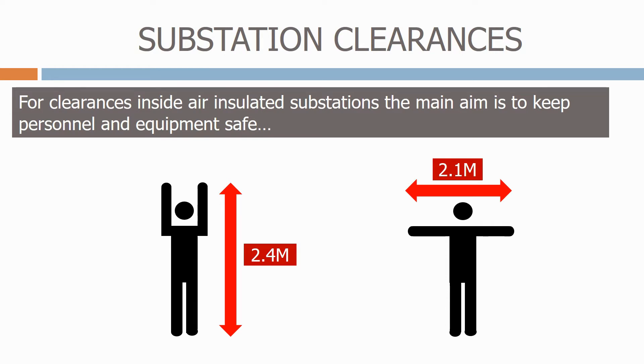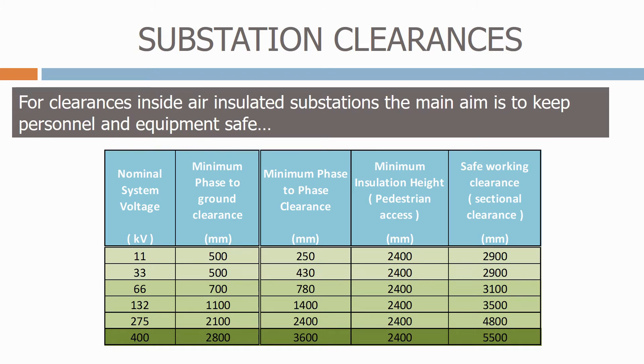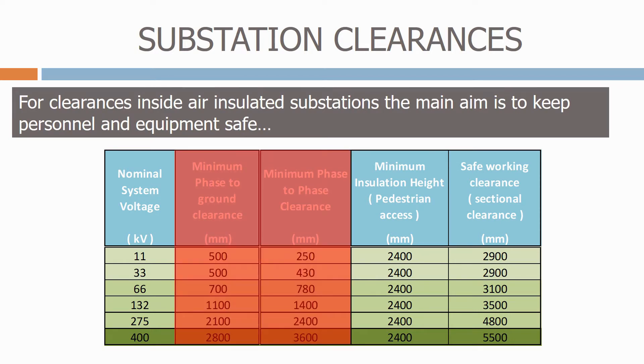Let's now look at a typical utility's table of electrical clearances. As you would expect, as the system voltage increases, all of the electrical clearance distances also increase. In the first two columns, we have the minimum phase-to-ground clearance and the minimum phase-to-phase clearance. These are purely design clearances, and are used to define the minimum distances between the electrical equipment.